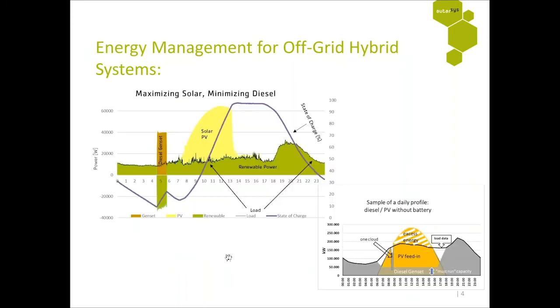What I have to tell you is the functionality of the battery is seen on two sides. One is that you have to balance the fluctuations over the daytime, meaning the fluctuations of the solar from minute to minute with clouds or something like this. The second is we have to shift the energy from the daytime to the nighttime. Both functionalities are very, very important. Otherwise you stay with the PV generation at only 20 to 30%, because otherwise you cannot balance this small grid, as small grids are really affected by these fluctuations.